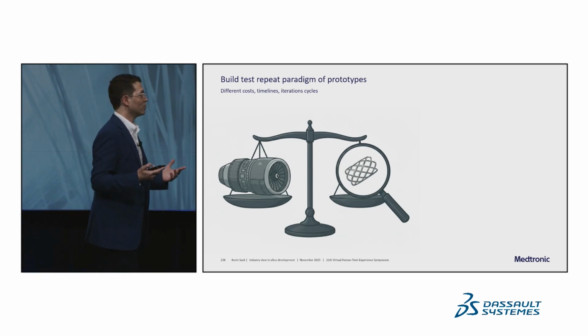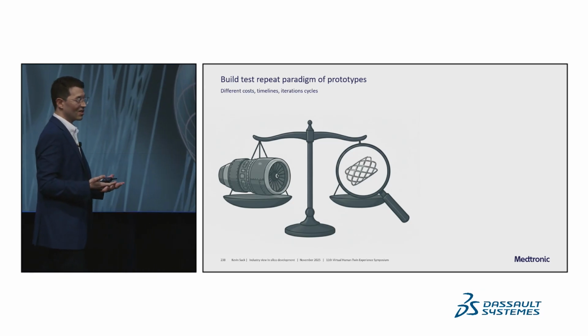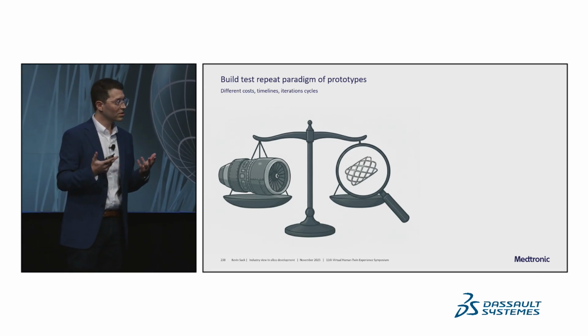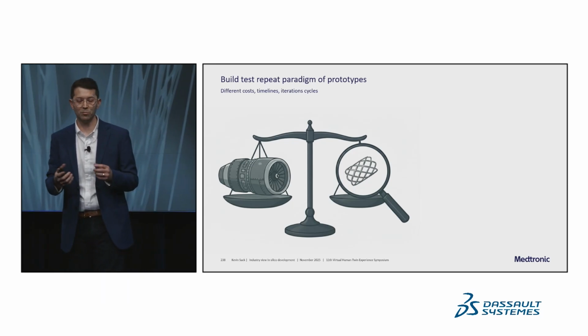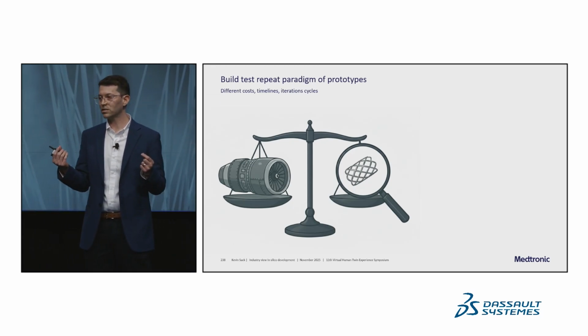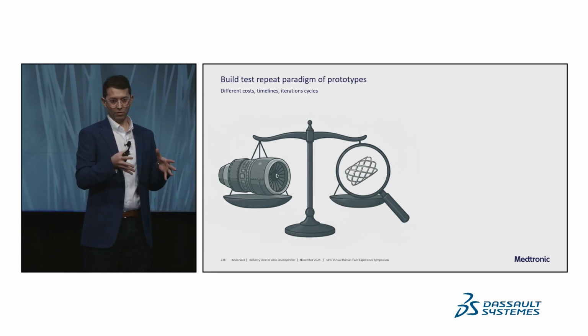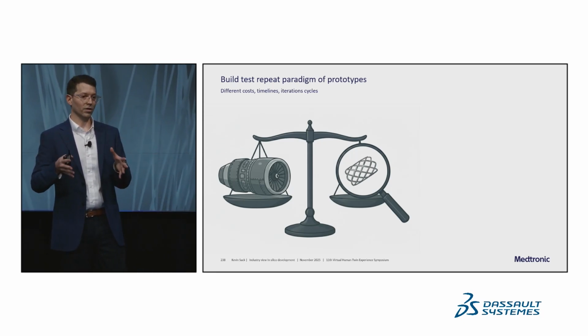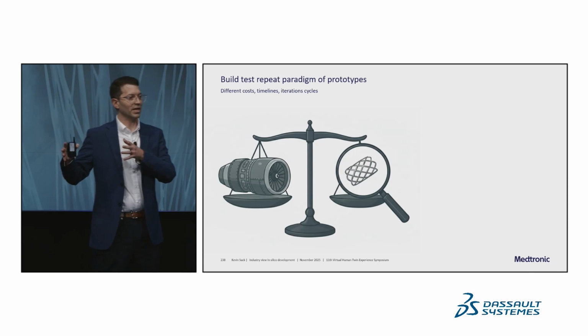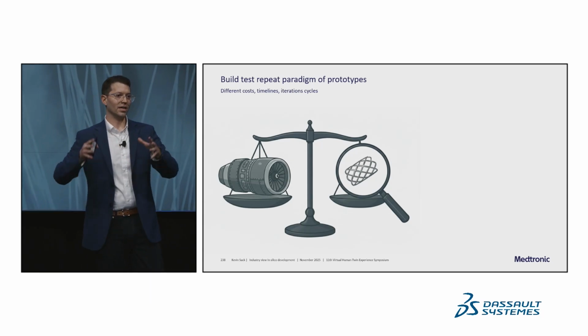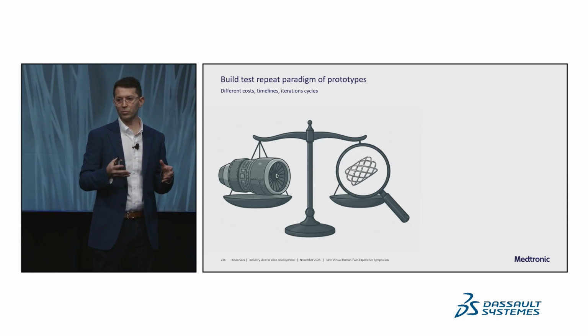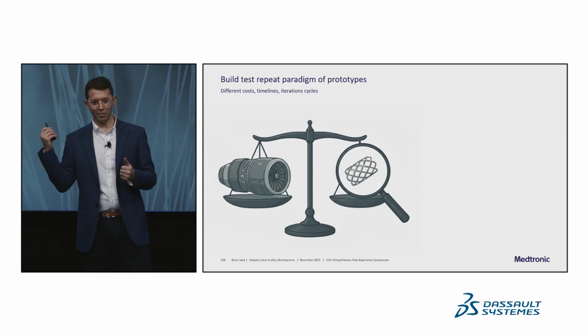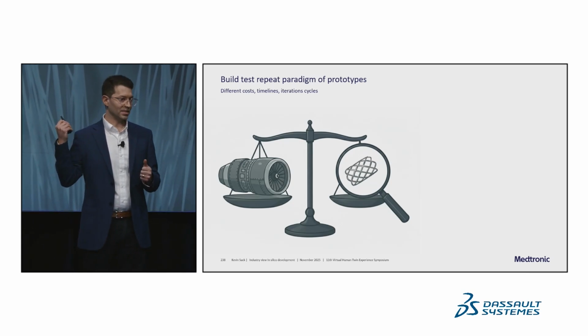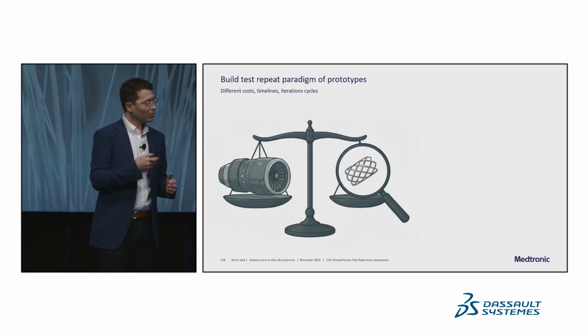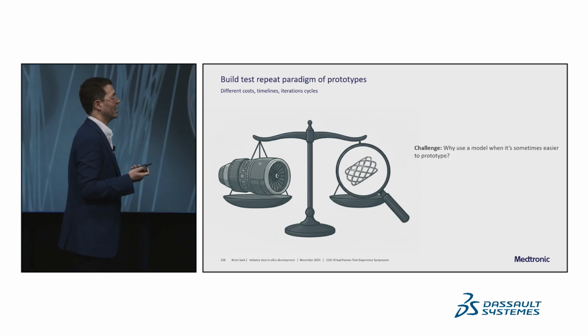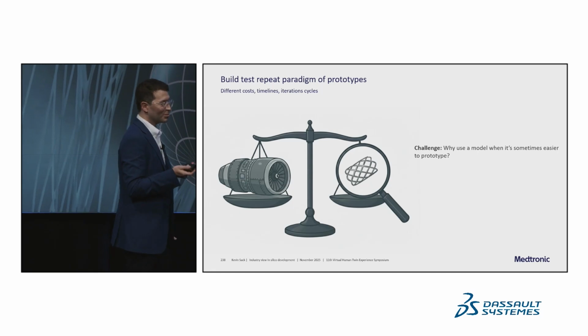Compare that with maybe a coronary stent, which, to be honest, costs in the dollars. Right? It's not expensive. It comes from nitinol tubes that we laser cut. In fact, if I have to model one of those, it will probably take me longer to do all the V&V 40 applications that I need, from meshing and verification all the way through to I get a model that's usable, than it will be for some of our prefab engineers to mock up a few in the lab and test them. Right? So that's one of our first challenges, is that sometimes in healthcare, it might be easier to just build a prototype.